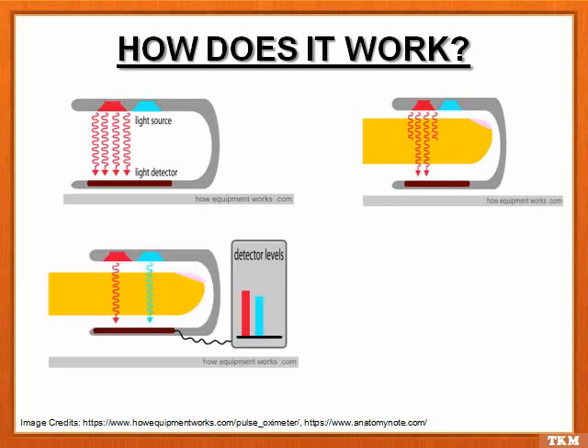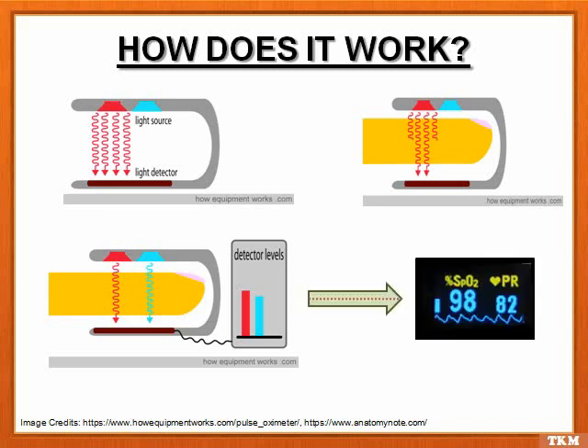This light source sequentially passes light of different wavelengths through a sample of oxyhemoglobin. The pulse oximeter detector works out the oxygen saturation by comparing how much red light and infrared light is absorbed by the blood. The pulse oximeter computer takes these factors and computes the saturation.